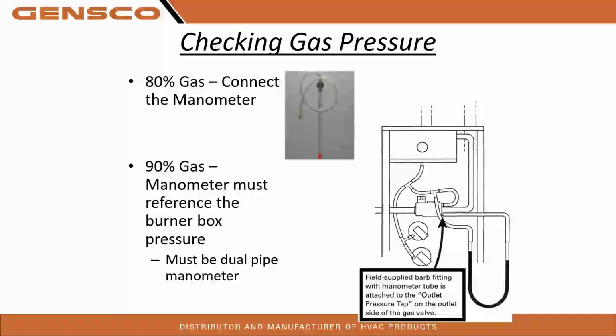Okay, so we're going to check gas pressure on an 80% gas furnace. We're just going to connect the manometer straight to the gas valve. When we get into 90 or sealed combustion units, we are going to reference the burner box. We don't have these on the new style S because we do not have sealed combustion. So you're going to plug straight into the gas valve on those models. You get into the older legacy stuff, you're going to reference the burner box for sure. You have to have a dual pipe manometer to make this work and a T-fitting.